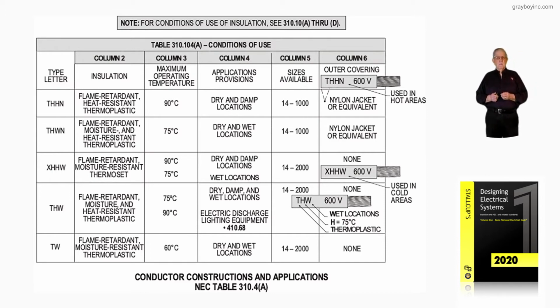It's nothing to be 35 or 25 below zero. The group of electricians asked me, "Hey, Stallcup, could we use THHN up here?" And I said, yeah, you could do that. And they strung THHN between 2 buildings and XHHW. Let it stay there all night long with that temperature dipping down like that.